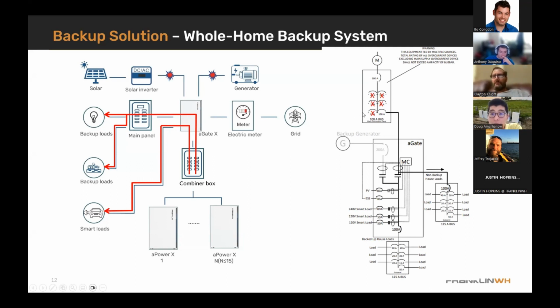So the idea is if you can relocate all your loads and have your 100 amp service act purely as a pass-through, with your loads relocated to the backed up or non-backed up side on the A gate, you can add more loads to the A gate and rely on that microprocessor to make decisions and balance the home power sources. That's allowed as of right by National Electrical Code.